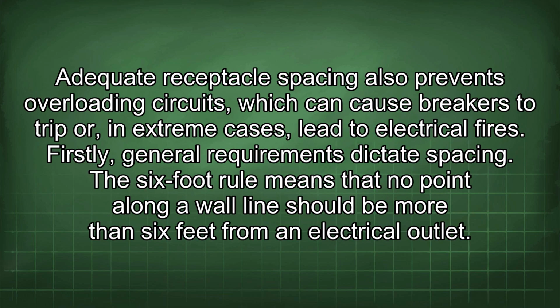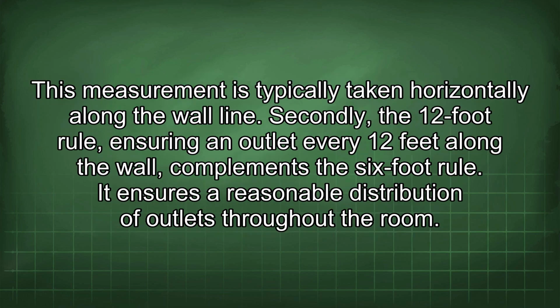Adequate receptacle spacing also prevents overloading circuits, which can cause breakers to trip or, in extreme cases, lead to electrical fires. Firstly, general requirements dictate spacing. The 6-foot rule means that no point along a wall line should be more than 6 feet from an electrical outlet. This measurement is typically taken horizontally along the wall line. Secondly, the 12-foot rule, ensuring an outlet every 12 feet along the wall, complements the 6-foot rule. It ensures a reasonable distribution of outlets throughout the room.